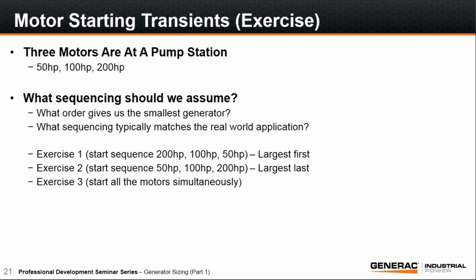So if we were to look at an application and we had 3 motors, let's just assume it's at a pump station. So we've got a 50, a 100, and a 200. I discovered over time that a lot of manufacturers out there will tell you, well, you always start the biggest motor first.